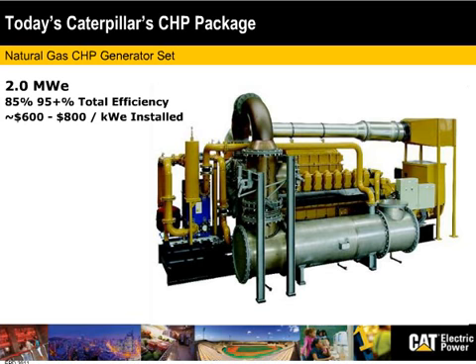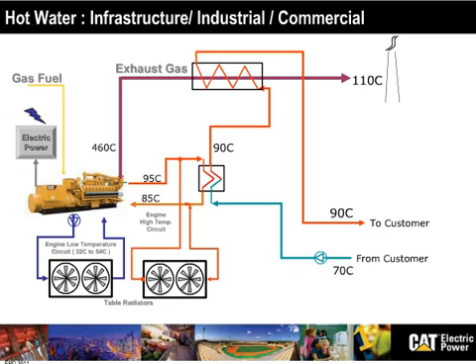What is the most popular media people would like to recover the heat from a CHP? And the most popular media is hot water. Hot water is very useful in infrastructure, in industries, and commercial applications. So here you'll see how a customer will return water at 70 degrees C back to the CHP system that will take the heat first from the jacket water and then from the exhaust gas and brought this water back at 90 degrees C back to the customer and providing power, heat power, thermal power, and value to that customers.